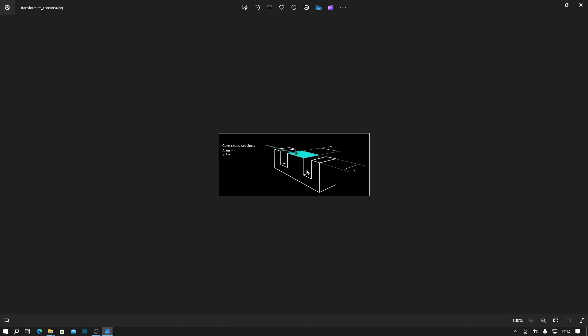Here's a representation of the actual laminations as they would be stacked up inside the transformer. The dimension that we're interested in is the core area, so this is the cross-sectional area of the core that goes through the central part of the transformer, and it's purely this area which is used to determine the power rating of the transformer.